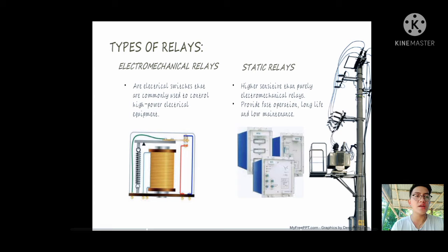Static relays are more sensitive than purely electromechanical relays. Also, static relays provide fast operation, long life, and low maintenance. Si static relays ay meron siyang no moving parts and minimeasure niya yung elements of the static relays, from the diodes, Zener diodes, or the PNP and NPN transistors, and also other combinations.